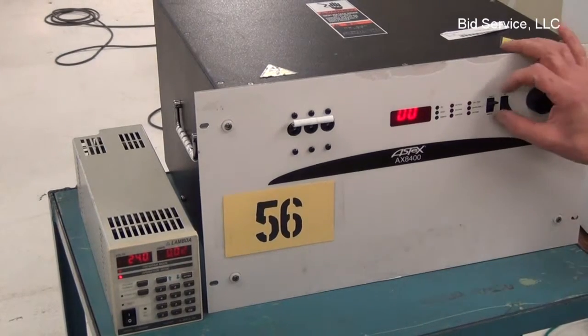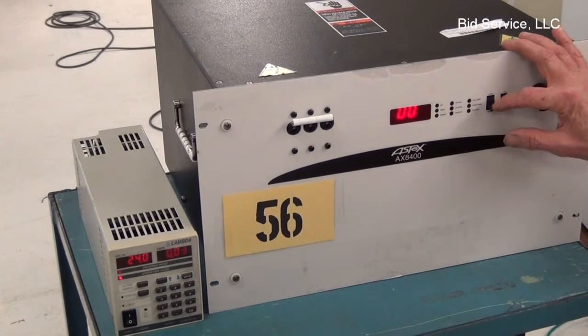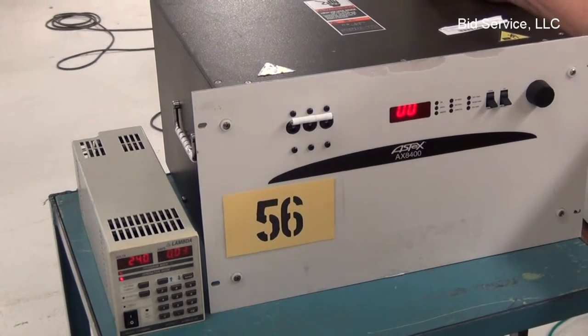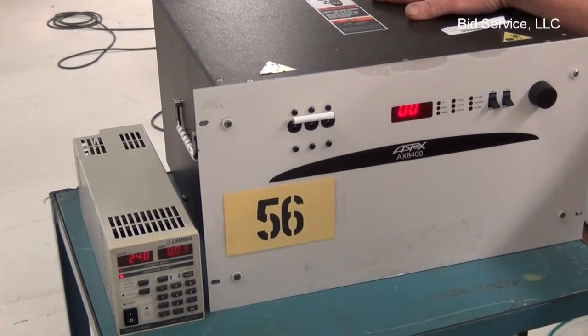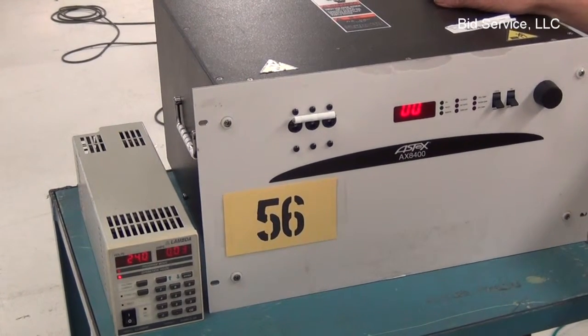It has a local and remote switch. The remote switch allows you to use the interface port on the back to control the ozone generator from a remote position or possibly from a computer.